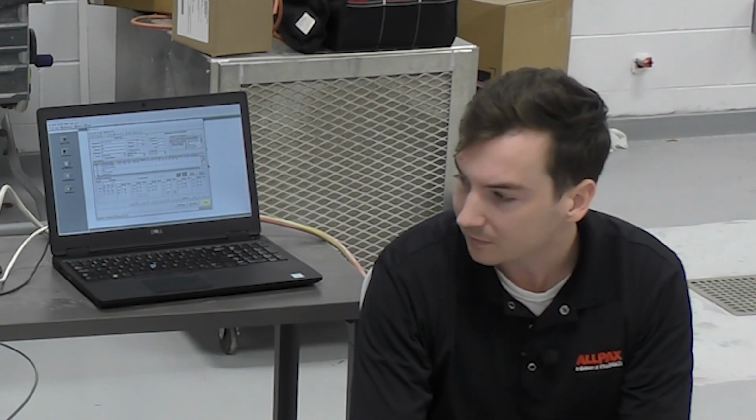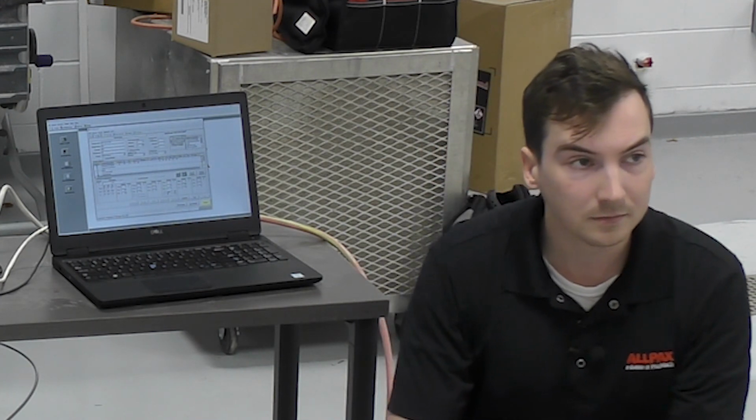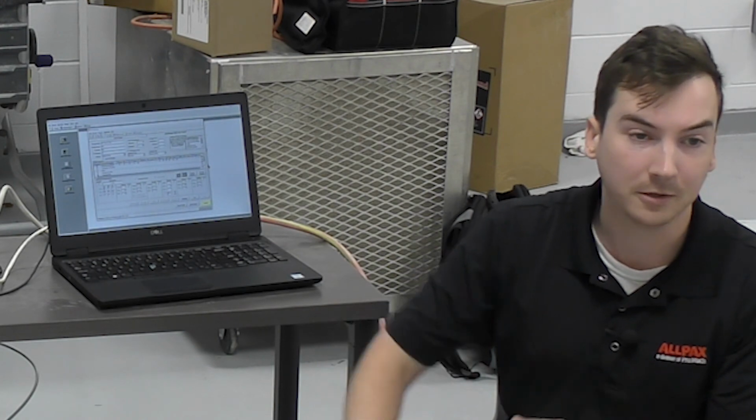I've not seen it have any problems with filling up with condensate, but maybe you have a day where the steam is extra wet in the pipes or something like that. The flow control can be adjusted so it takes longer for the drain to close. I may have to talk to you later about how to do that on mine. Anyway, if you have a pneumatic valve on your drain, it's just a little flow control you can tee into the return air on the dual action pneumatic valve, and it just keeps it closing slower. And you can just adjust it.